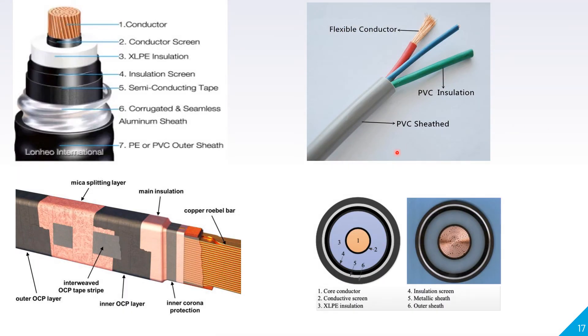In a cross-sectional view of the cable, the layers are: conductor, conductor screen, XLPE insulation layer, insulation screen, semi-conducting tape, seamless aluminum sheath, and PVC outer sheath. The insulating material ensures that leakage current does not come outside or come in contact with anyone.